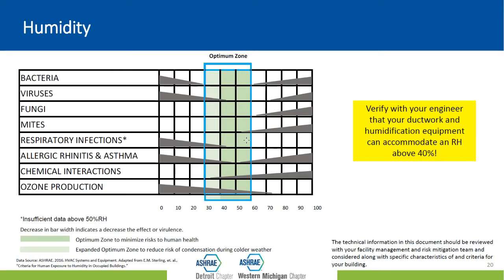Now, some facilities may have single pane doors, or they may be a place with a lot of ornate furniture, a house of worship, for example. You want to make sure in those spaces that you don't create a problem by increasing your relative humidity. If you've got concerns about condensation in colder environments, then you may not want to increase your relative humidity to 40 to 60% in the winter time. Maybe you're going to have it around 30%, right?